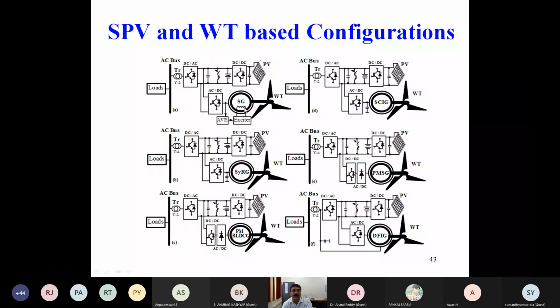But if we are connecting things like here, the DFIG is connected on the AC side also. The stator of the DFIG is connected because, being a doubly fed induction generator, we are extracting both its rotor power and stator power. The rotor side can be controlled through the DC link, and the stator power can be fed directly to this point. Here we need a synchronizer, so these kinds of configurations can be used.